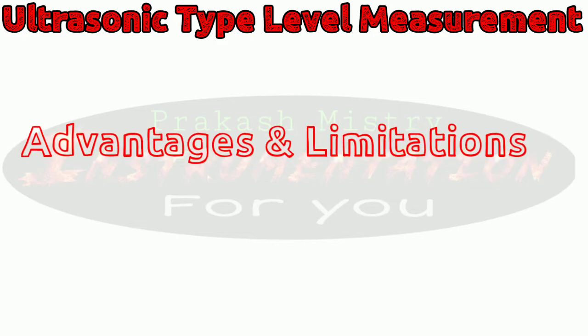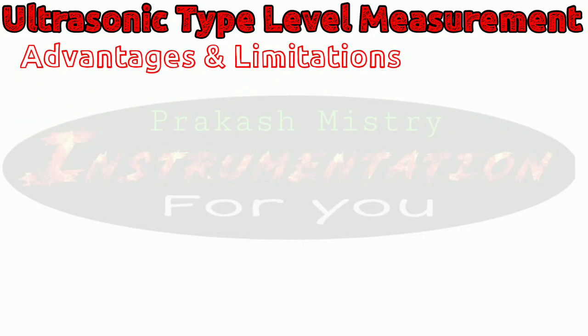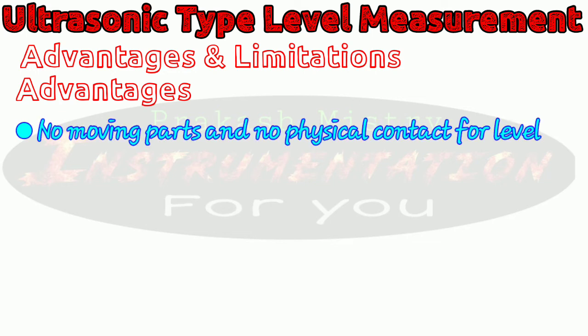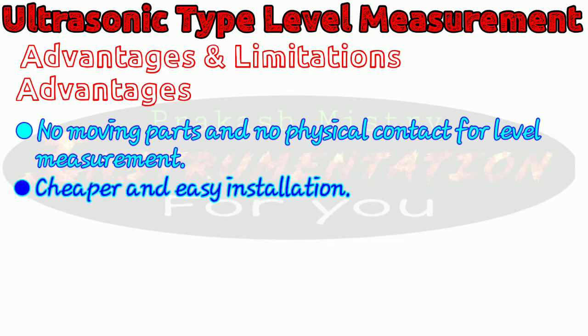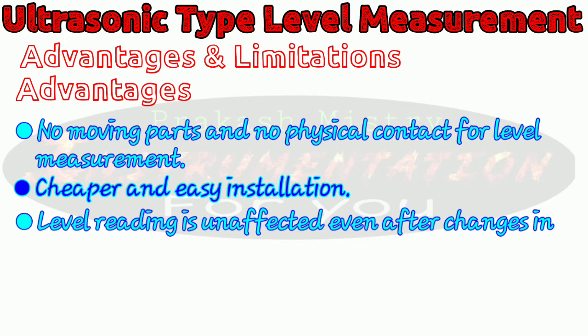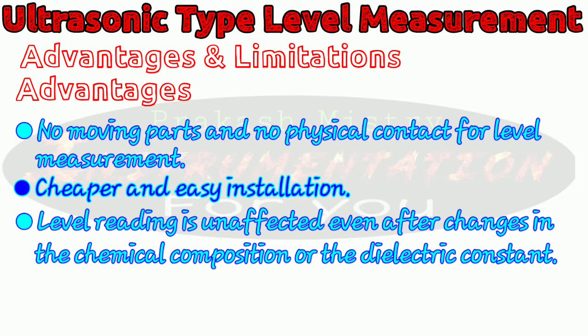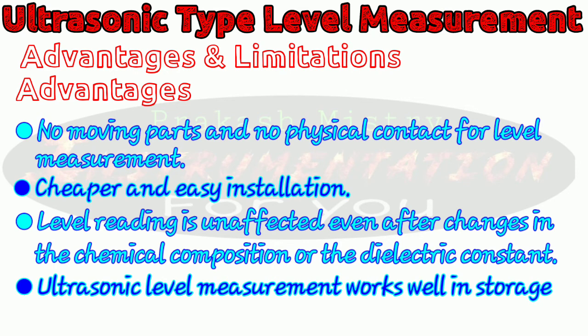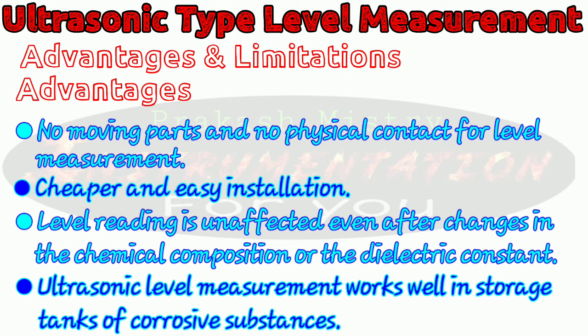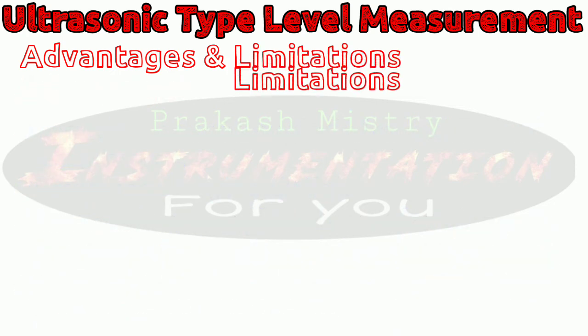Now let us look at the advantages of ultrasonic type level measurement. First, the ultrasonic level transmitter measures the level without making physical contact with the product. Second, the ultrasonic transmitter is cheaper compared to a radar transmitter and is also easy to install. Third, there is no difference in accuracy due to changes in the chemical composition or dielectric constants of the process fluid. Ultrasonic level measurement works well in storage tanks of corrosive substances such as hydrochloric acid, sulfuric acid and caustic soda, though one must ensure the sensor material is chemically compatible.